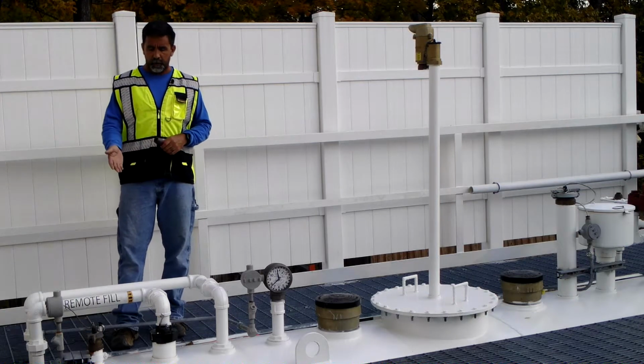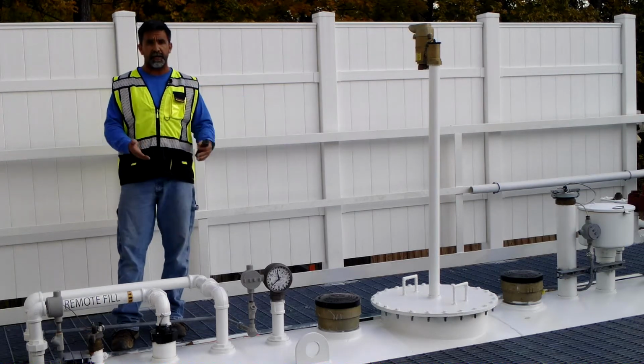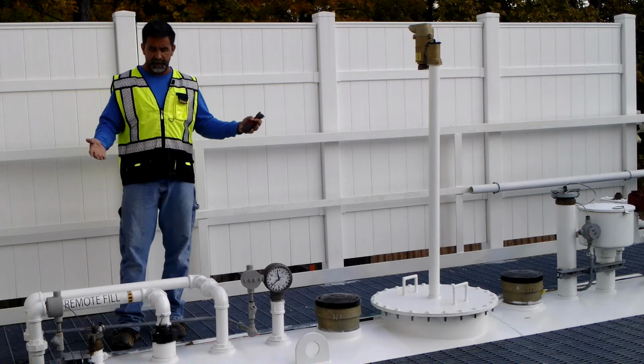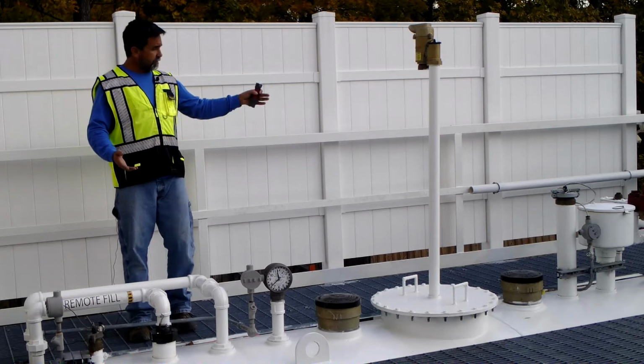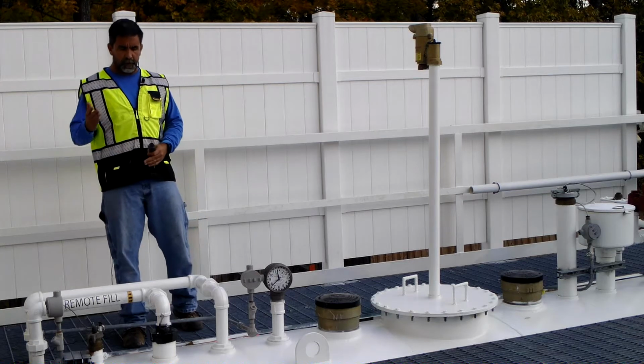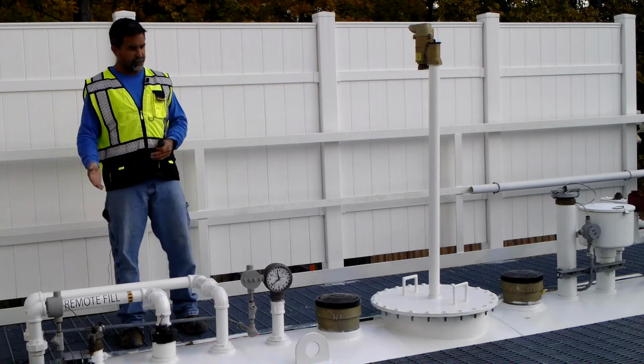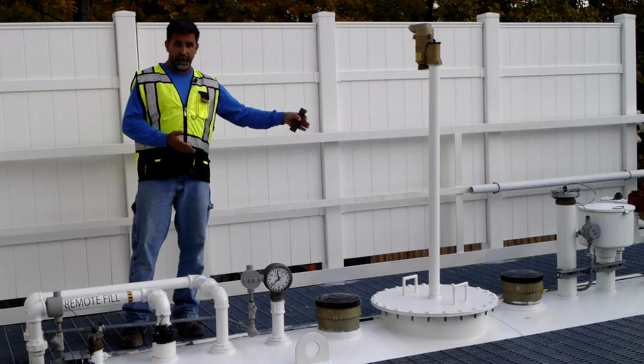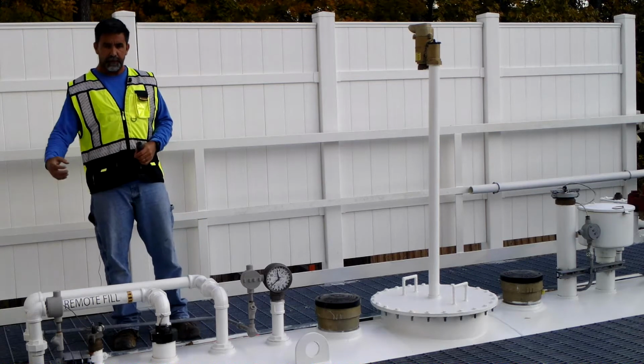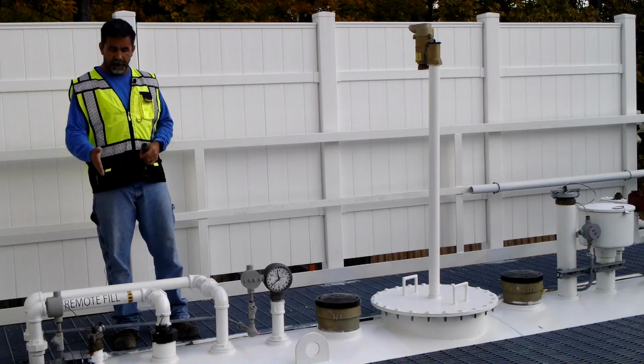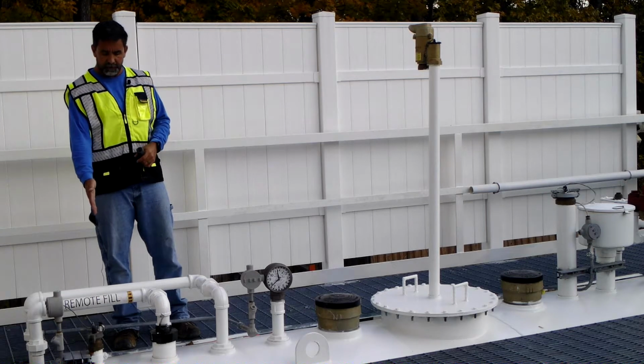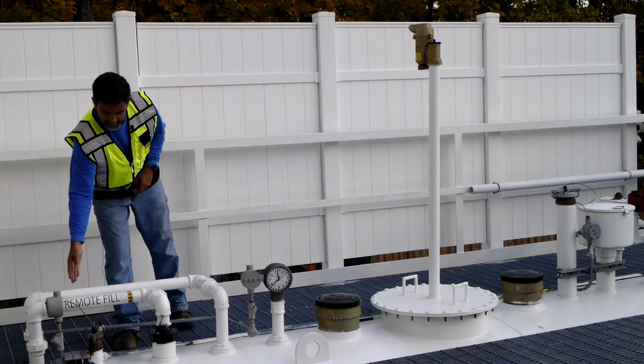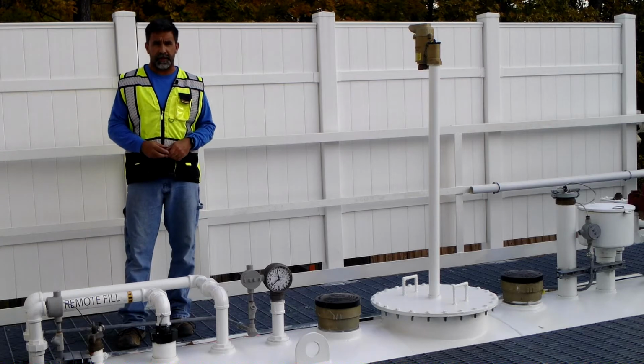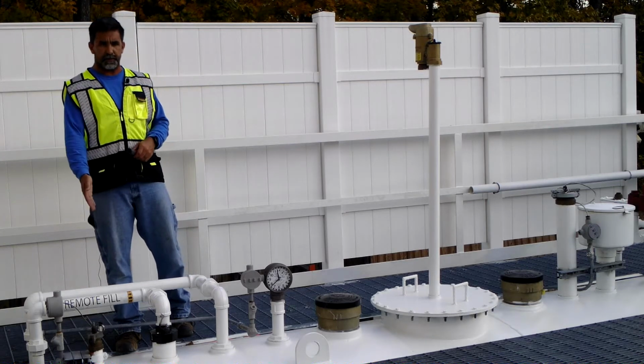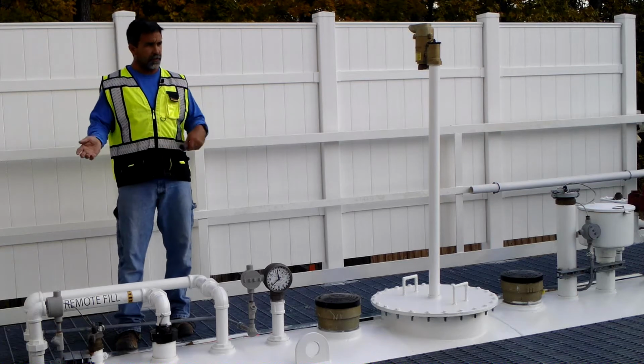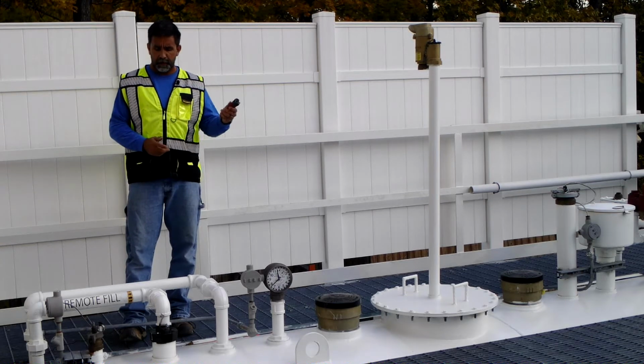So the first thing we want to do is identify where the interstice and the riser are for this tank. I would go through all the different components, and I would always want to be looking on one end or the other. It's rarely going to be in the middle of an above ground tank. It's usually going to be on the end with an external pipe, or right near the end. In this case, it is right here on this end, and we can see this wire going down in, which is also another indicator showing me that there is a wired sensor in the tank interstice being monitored remotely by a tank monitoring system.